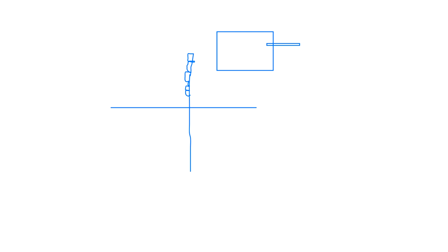But if the pump is already at a higher pressure rating, then we have to put the setting into the controller that the pump will start at this much pressure and it will stop at 160 psi or 175 psi. So the pump will work accordingly. And if the pressure goes higher than that, we have the pressure relief valve for the diesel pump and for the variable speed electrical pumps. So this will not allow higher pressure into the fire protection system.